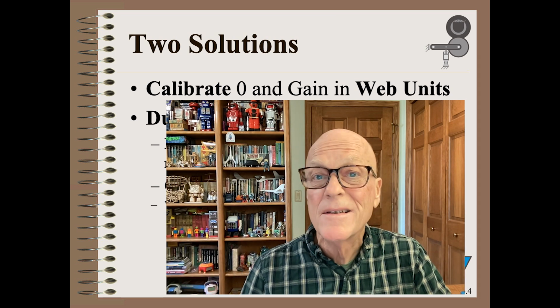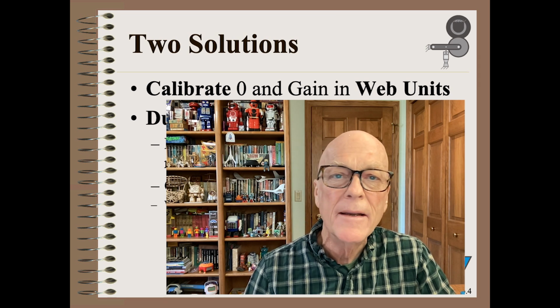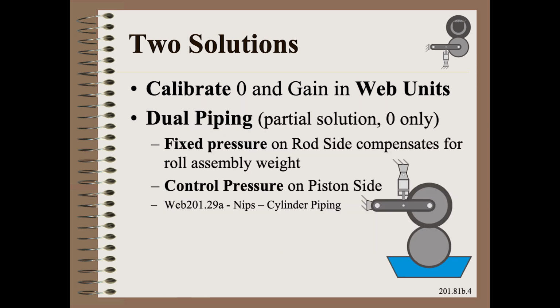There are 2 solutions to this confusion. Obviously, the very best is to calibrate zero and gain in web units of kilonewtons per meter or PLI in the English system. Computers can do this in microseconds. There is an old school workaround that uses dual piping as described in Web 201.29a. While this is a super great idea in any case and for many reasons, it only fixes the 0 part of the problem, not the gain.